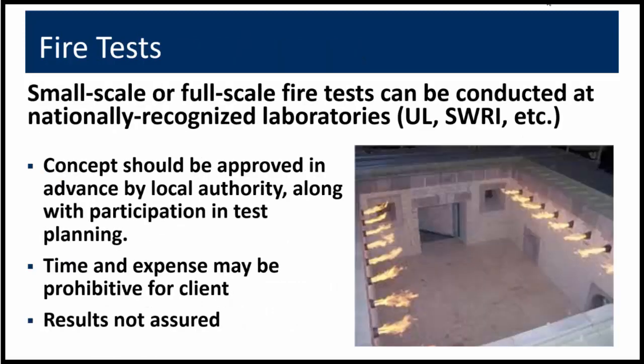Performing fire tests is generally the last resort because of the time and cost involved. WJE is currently involved in arranging a test for an assembly which differs from the published tests and where the local authority is looking for a test or report from a nationally recognized fire testing laboratory. It's important to involve the local authorities in the planning of a test to make sure it will be approved if successful. There's no assurance of the outcome or if the local authorities will approve the result, so this is something to avoid in the interest of the client's budget and schedule.